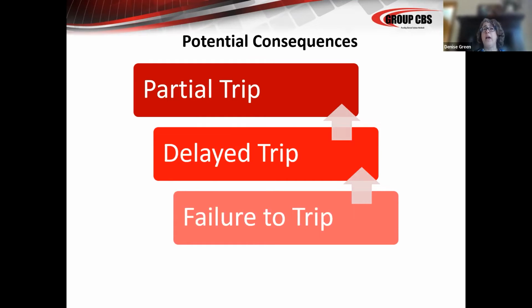So instead of it tripping at 3,000 amps that the trip unit was set at, the fault escalates. And because it didn't trip as quickly as it was supposed to, because it wasn't lubricated properly, now your fault is 8,000 amps or 10,000 amps. So that's a very different event for the circuit breaker and for the contacts in the circuit breaker to deal with. So it's much harder on your equipment and can cause damage to your equipment because the breaker isn't opening quickly enough. So all of those design features of a circuit breaker are based on its capabilities of interrupting and how quickly you can interrupt a fault. So that's a potential problem with a delayed trip.